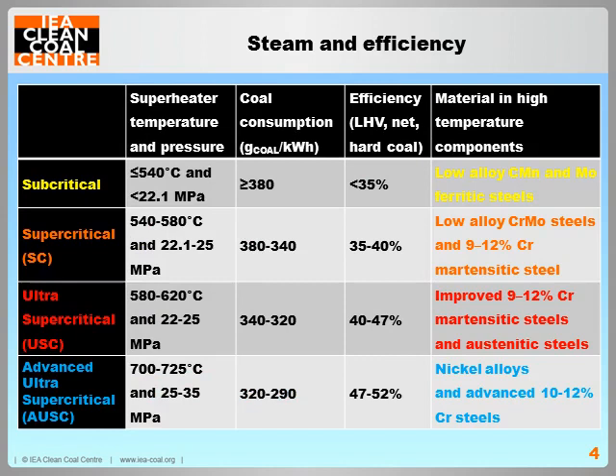However, the maximum steam temperature is limited by materials that can operate in high temperature conditions for practical service lifetimes without failure. Historically, steam temperatures have been increased to superheat steam temperatures of 600 degrees Celsius through improving steels. But further improvement has been insignificant and the steel barrier has been reached. Fortunately, nickel alloys can be used in place of steels in the highest temperature components to reach higher steam temperatures.